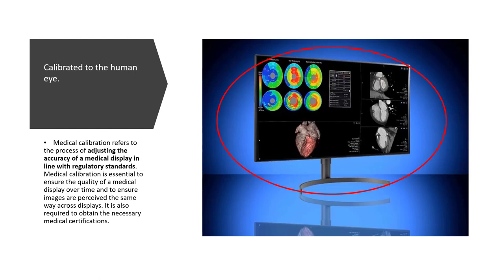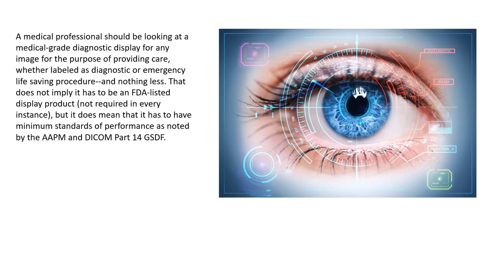Colors or shades of gray of the images are presented on a medical imaging monitor. That monitor is calibrated to the human eye. A medical grade professional monitor should be used by individuals interpreting the information off the display. That does not imply it has to be an FDA listed display product, but it does mean that it has to have minimum standards of performance as noted by DICOM part 14 grayscale display function.